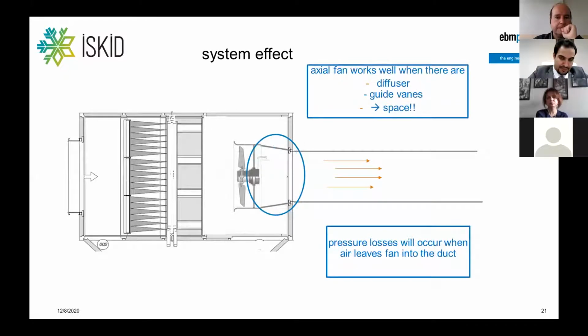If you use, for example, an axial fan, this might be a good option if you have enough space to use a diffuser, and if you connect it directly to the duct system. If you connect it directly to the duct system, you can make use of the dynamic pressure. You can regain it and reuse it and create a static pressure out of it by using the diffuser. And so in some applications, an axial fan could be a good option, but not in any case.